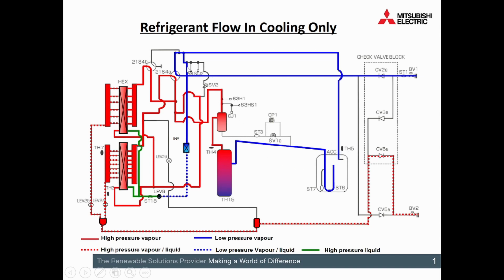Just a little side note here. On these units, the actual inverter is cooled with the refrigerant, so I'll bleed off some of that refrigerant that should have been going to the indoor units at this point here via LEV9, and I use that to actually cool the inverter itself. And it's only going to start doing that when the actual inverter gets decently warm. Anything above sort of 75 degrees, other than that, it doesn't actually touch it.